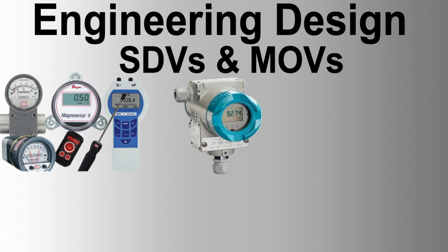Hydraulic pump motor. The motor of the hydraulic pump shall generate the required pressure in the hydraulic system. Equipped with elements for electrical protection, start-stop facilities controlled by local hydraulic pressure, an on-off switch, local indicators for power supply and availability, and potential free contacts for remote failure annunciation. At least 2 junction boxes shall be provided, one for power connection and one for status signals transmission.